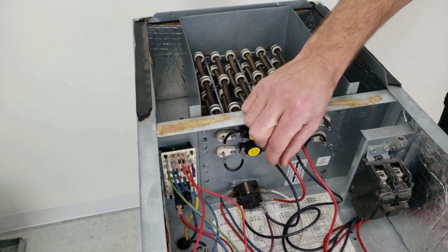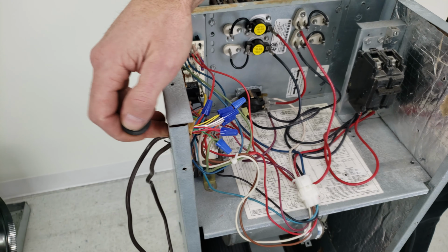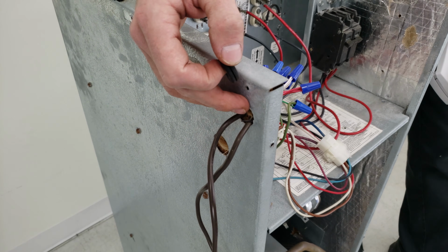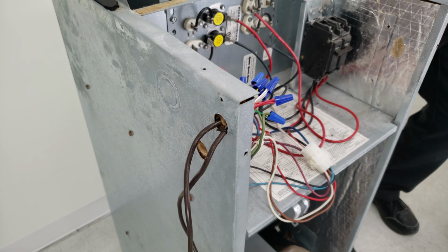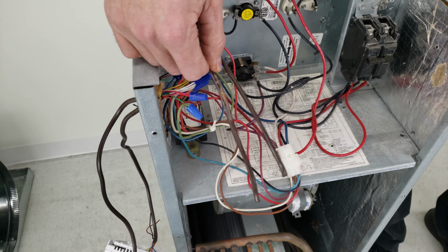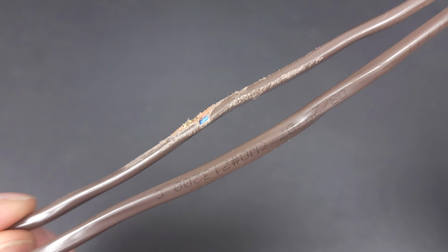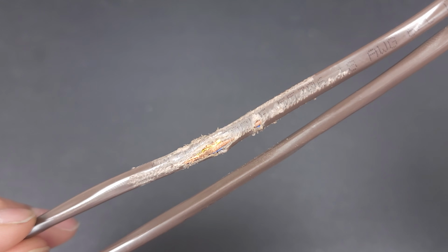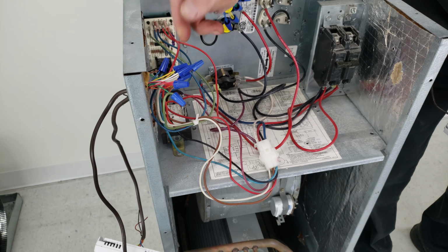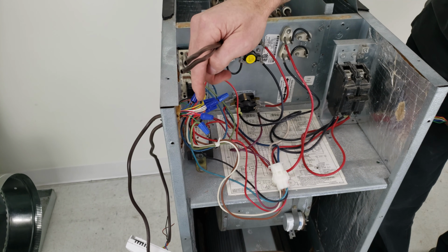As far as the thermostat wire, you want to have a rubber insert over here on the side where the thermostat wires are coming through. They could become chafed right there, and you could have thermostat wire that looks like this. That's chafed thermostat wire, and that could be the result of maybe a mouse or a weed whacker outside. So you want to wiggle the thermostat wire while you're trying to get the system to operate, to see if there's a problem there.